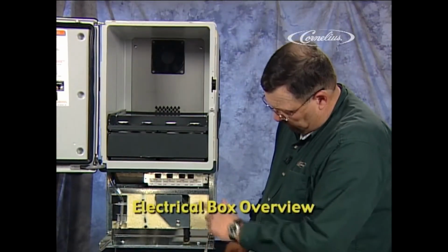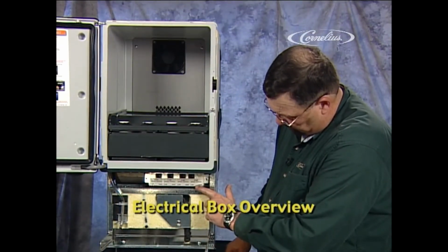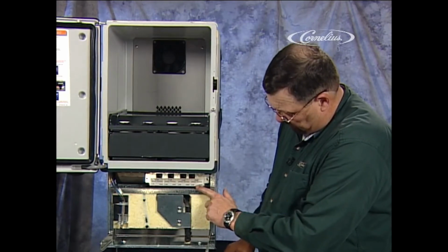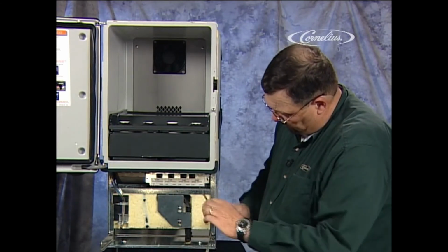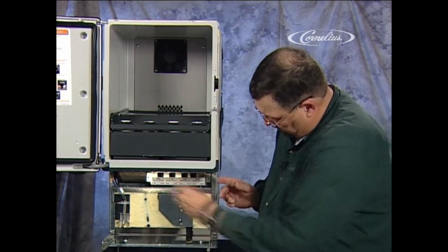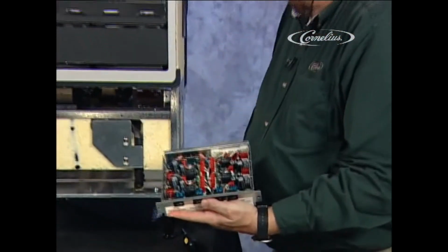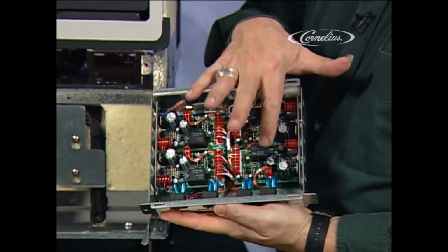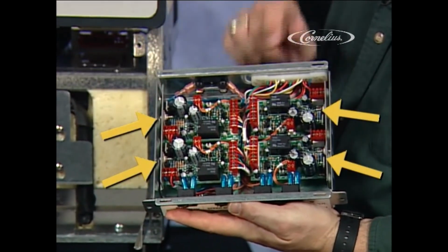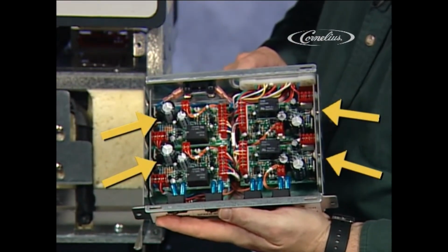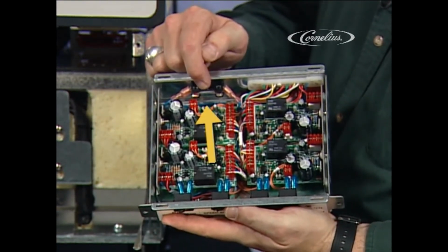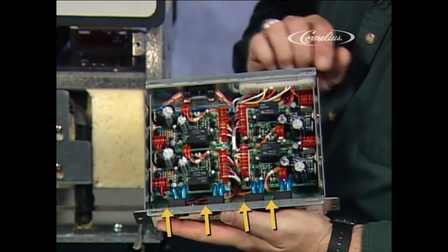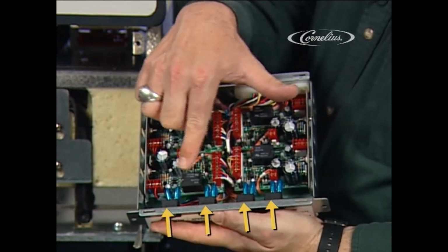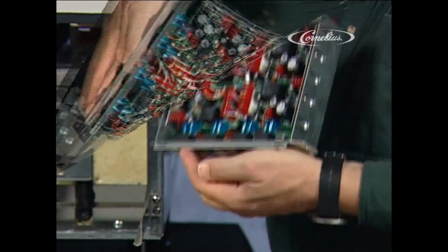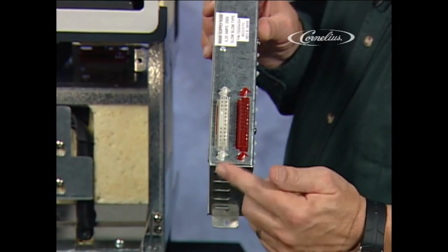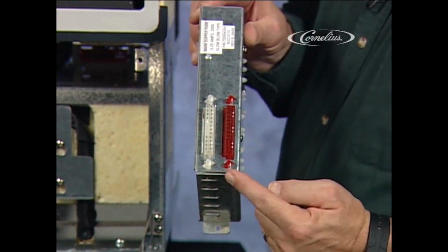The electrical box is located in the lower right corner of the unit, mounted to the water bath tank cover, held in place with 1 screw. It's what we like to call plug and play. It contains the voltage regulator boards, VRB, for each pump head, a fuse, and speed switches for slowing down the pump motors themselves. The box plugs into 2 cable connectors. The white is the input side and the red is the output side.